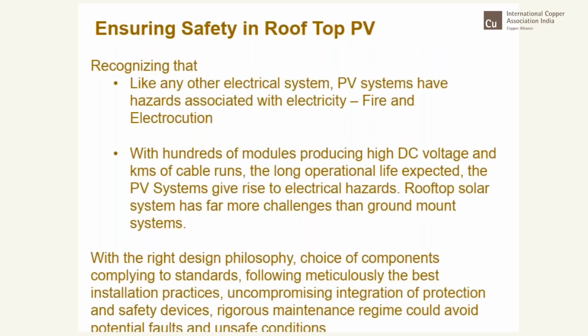And then ensuring safety in rooftop PV is recognizing that, like any other electrical system, PV systems have hazards associated with electricity, fire, and electrocution, and more so in PV, because as I listed earlier, there's a dangerous concoction of everything going wrong. You see water and electricity, a smooth surface, and despite your physical disconnect, there could still be electricity flowing, because the sunlight, the fuel, is continuously providing energy for the solar cells to generate. So especially when you have hundreds of modules producing DC voltages of high lethal value and kilometers of cable running, it becomes all the more a big challenge.